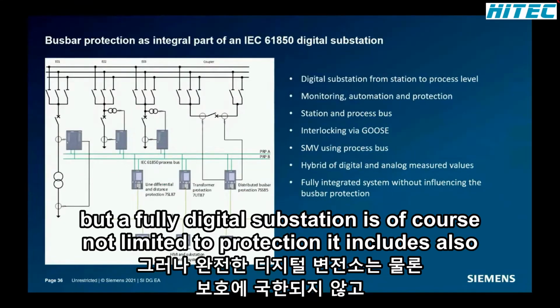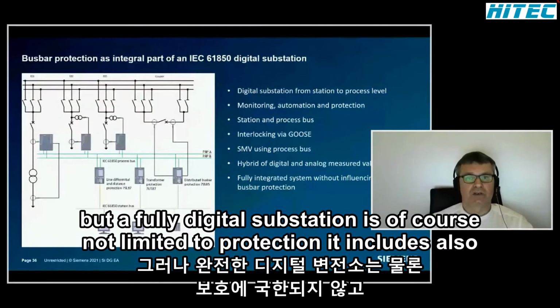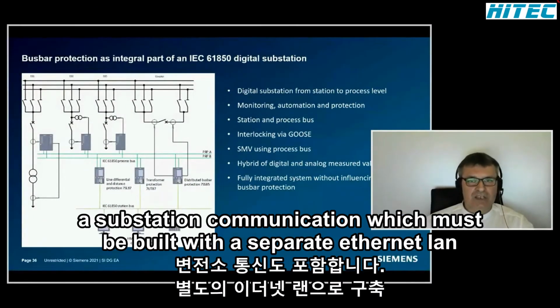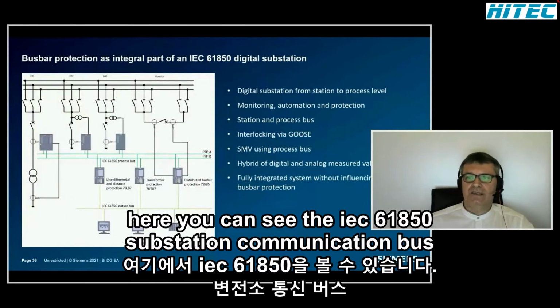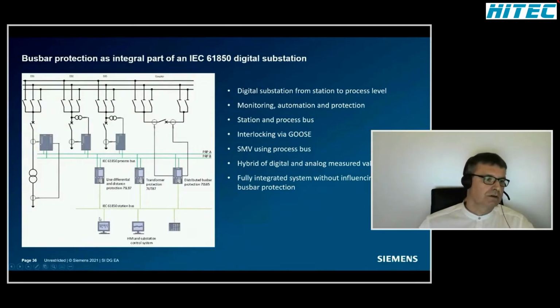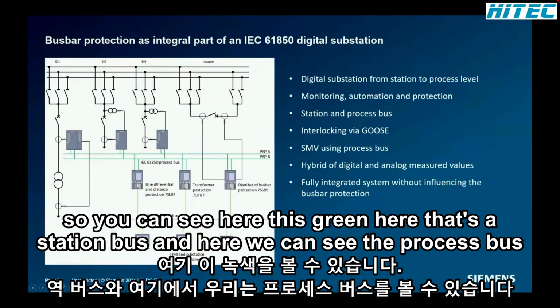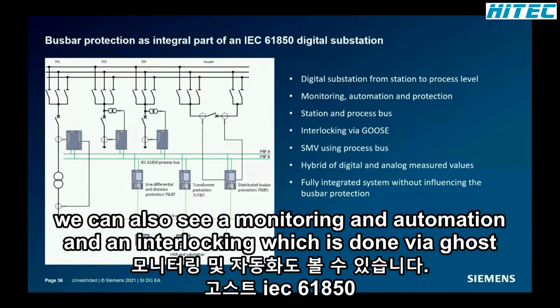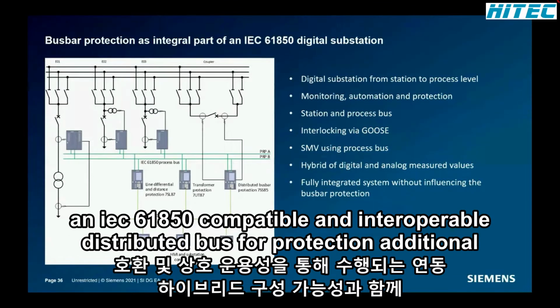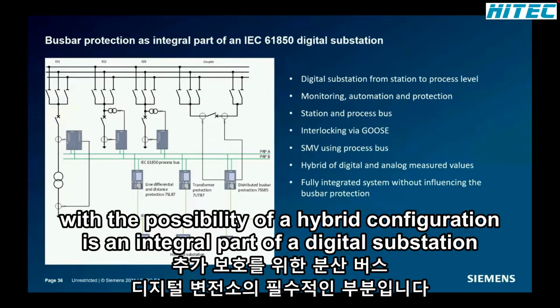But a fully digital substation is of course not limited to protection. It also includes a substation communication, which must be built with a separate Ethernet LAN. Here you can see the IEC 61850 Substation Communication Bus. So you see here this green, that's the station bus. And here we can see the process bus. We can also see a monitoring and automation and an interlocking, which is done via GOOSE. An IEC 61850 compatible and interoperable distributed busbar protection, additionally with the possibility of a hybrid configuration, is an integral part of a digital substation.